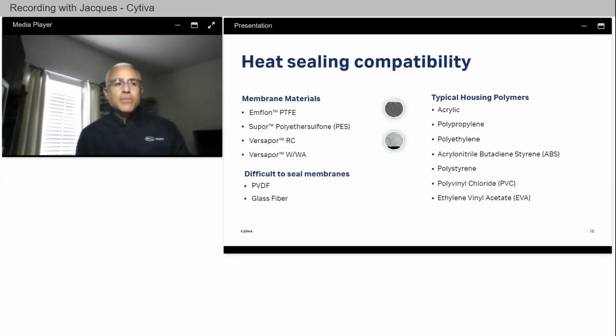So what types of microporous materials are most compatible with heat sealing? The list is broad, as it includes PES or polyether sulfone, PTFE, acrylic copolymer, polysulfone, nylon, and ultrafiltration membranes. We would also include PVDF and glass fiber as compatible with heat sealing, but we want to make you aware that the conditions in which these can be sealed can be somewhat challenging due to their physical properties. The housing materials that demonstrate the best compatibility with heat sealing with these microporous materials are listed here and include acrylic, polypropylene, polyethylene, ABS, polystyrene, PVC, and EVA.